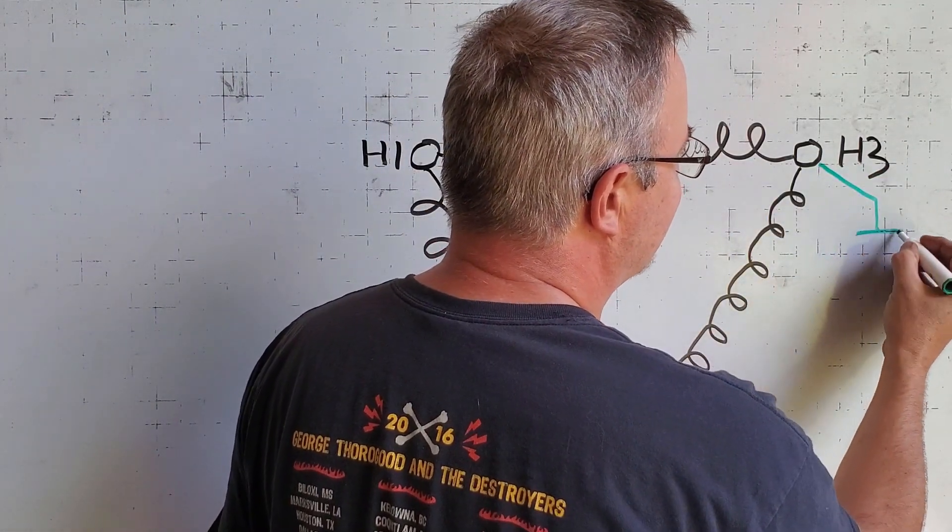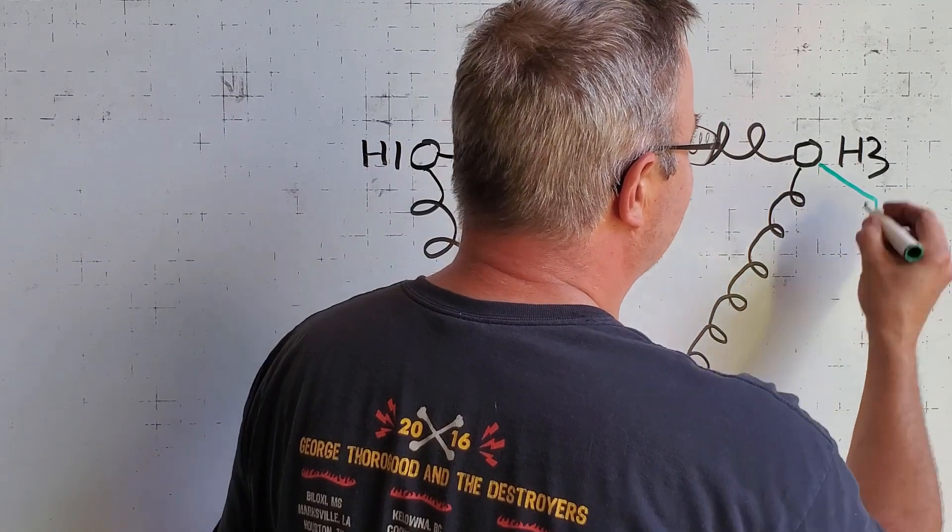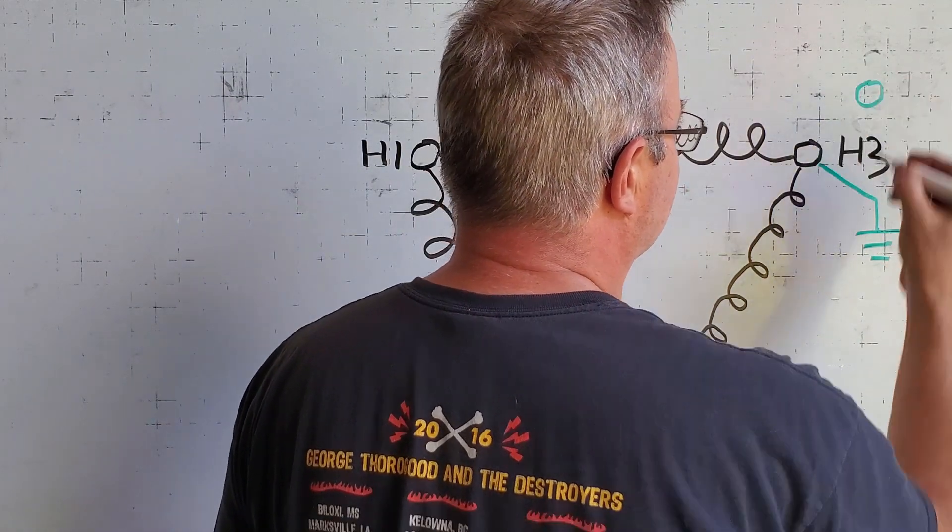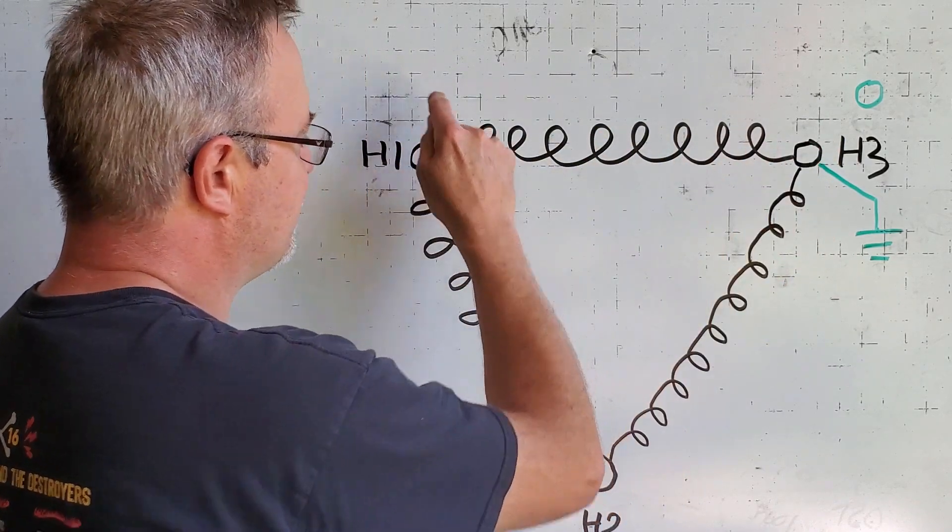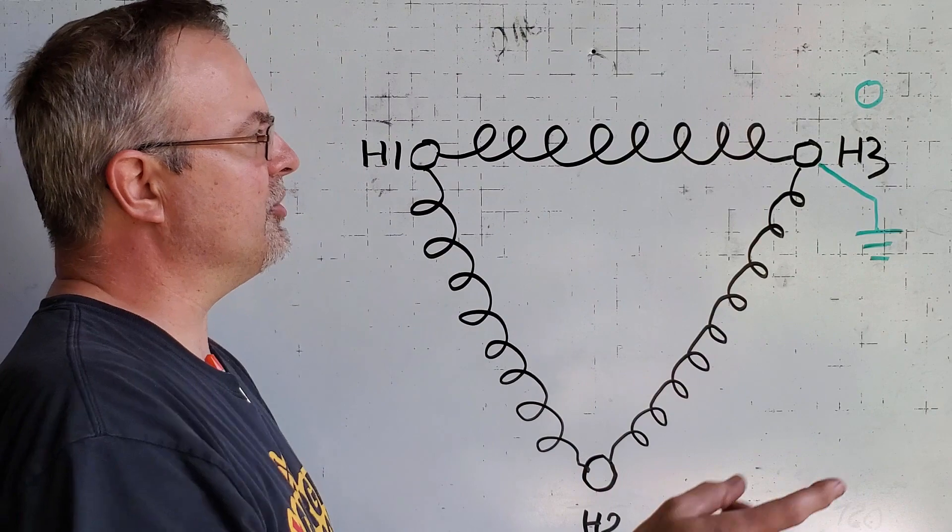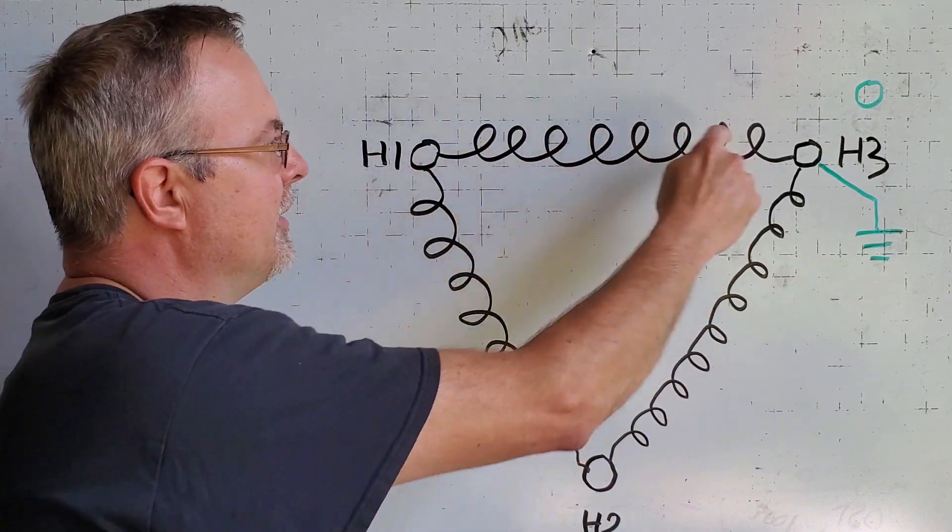But for the purposes of measuring voltages, he said to go ahead and we're going to ground this H3 point so we can say that this is going to be zero volts, and then we can read the voltages all along this coil up to H1.